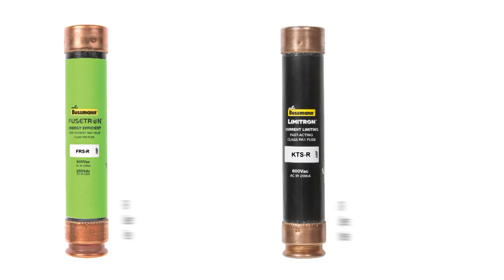For the most part, if a conductor's current carrying capacity is 20 amps, a 20 amp fuse is the largest that should be used to protect it. There are specific circumstances in which the amp rating is permitted to be greater than the circuit's current carrying capacity, such as in motor circuits. Dual element time delay fuses are permitted to be sized up to 175%, and non-time delay fuses up to 300% of the motor's full load current.